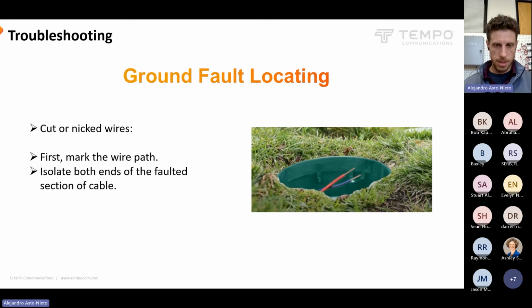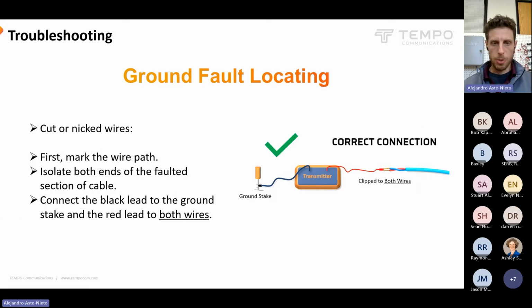Make sure you isolate both ends of that section of cable, so disconnect from decoders and anything else. You don't want that kind of voltage getting into these decoders or going to your controller. Isolate that section of cable, clip onto both wires here again, because if there's a fault on either wire, this will make sure to pick it up. If you do have decoders somewhere connected on this section of cable, in theory, there shouldn't be a big difference in voltage going across that decoder, but again, it's safest to disconnect anything you can.